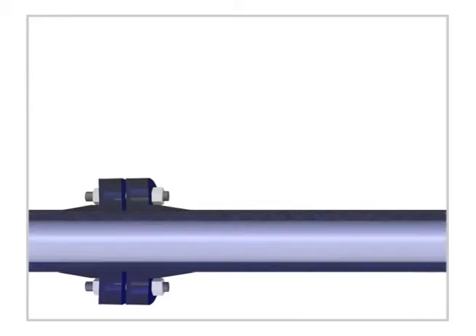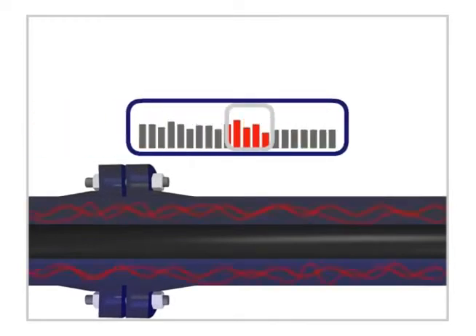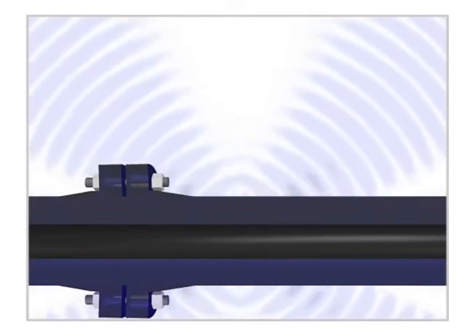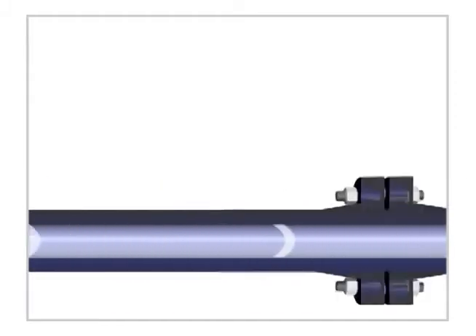Depending on the pipe diameter, material, and pipe wall thickness, some noise frequencies will radiate through the pipe wall and create sound waves that people can hear. It's important to remember there's also a secondary source of noise. For example, flow velocity at Mach 0.3 and above may generate noise independent of the valve trim. This must be accounted for, predicted, and controlled according to industry standards.